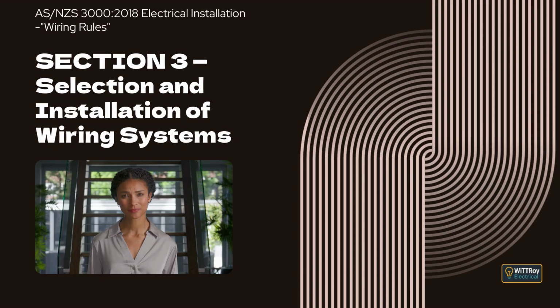Clause 3.9.4.1 General. This clause states that wiring systems installed where mechanical damage may reasonably be expected must be adequately protected, using the methods specified later in this clause group. Clause 3.9.4.2 Wiring systems near building surfaces. This clause explains that wiring fixed or restrained close to walls, floors, ceilings, or roofs must be protected if it is within 50 mm of the surface. The intent is to prevent damage from nails, screws, or similar fixings. The requirement does not apply where the wiring can freely move away from the surface if penetration occurs.